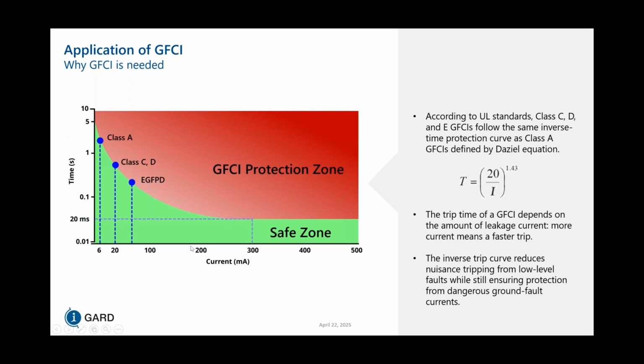So as we get more current, you can see that the different devices will trip at a faster rate to meet within the safe zone of this inverse time graph. The reason the inverse trip curve is used is because they want to reduce nuisance tripping from low-level faults, but still ensure protection for those dangerous ground faults that can happen instantaneously with a high level of current.